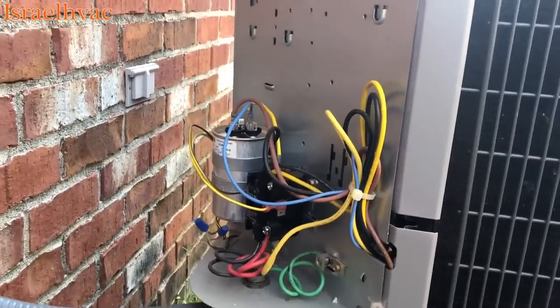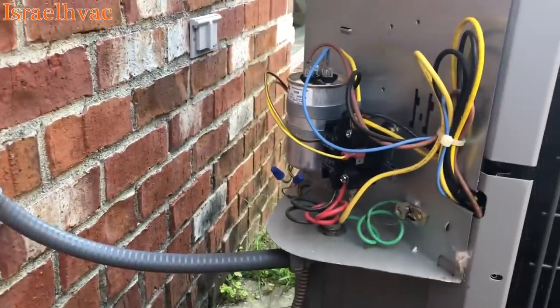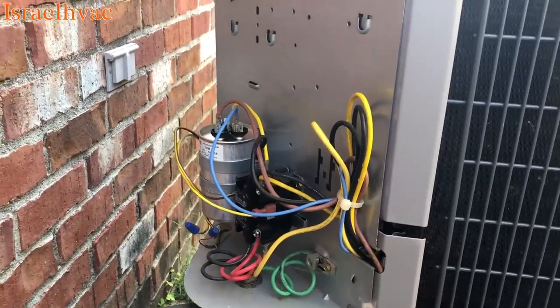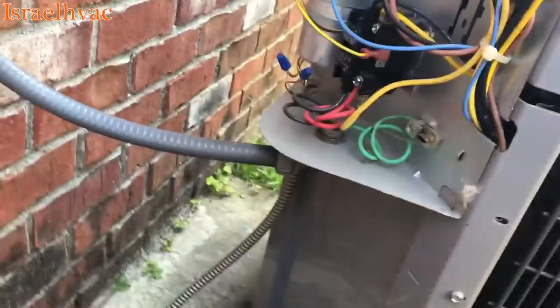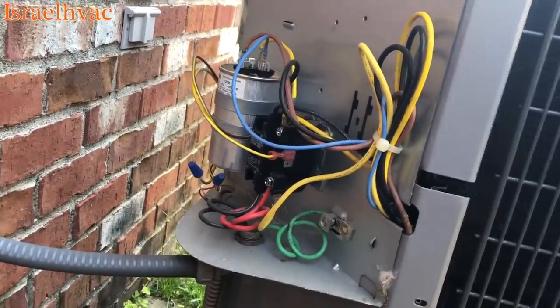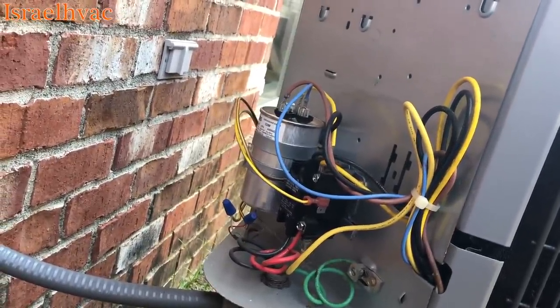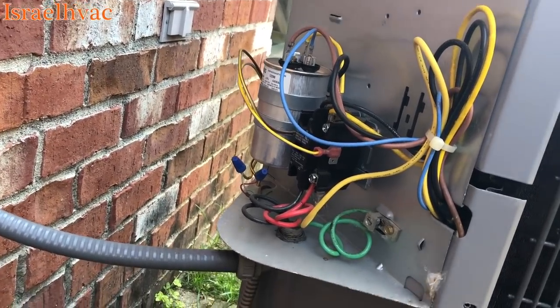I've been putting the Mars on for years and I have not had any issues with them at all. This capacitor will last — I'm not saying it'll last 10 years, but it'll last more than two and a half to three for sure. If you own your own company and you install ICP, Carrier, Bryant, or Goodman, do yourself a favor and rip that Chinese capacitor out and put in a better one, because this is warranty here.